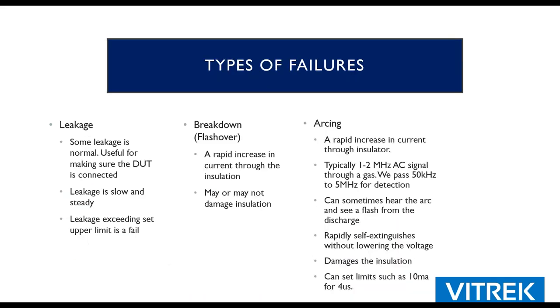All right, so types of failures. You can fail leakage. You go in there and you set a limit, and it might be 5 milliamps, and you connect your product, and for whatever reason, whether it's capacitive or resistive or both, you're at 6 milliamps. Okay, you're going to fail, and we have to figure out why. Is your setting wrong, or is your product built wrong?